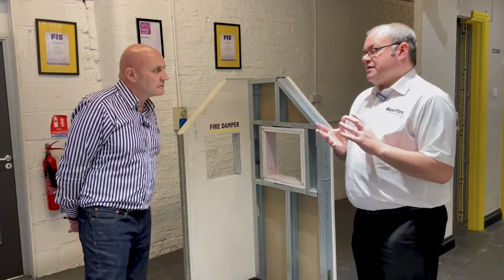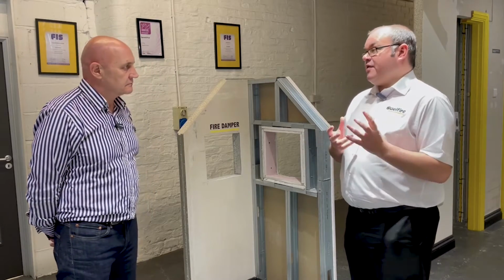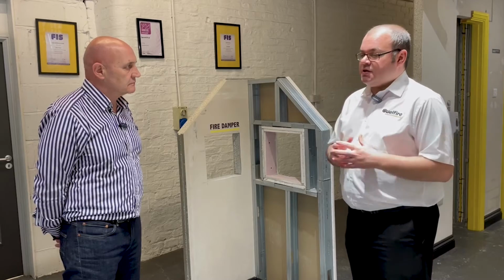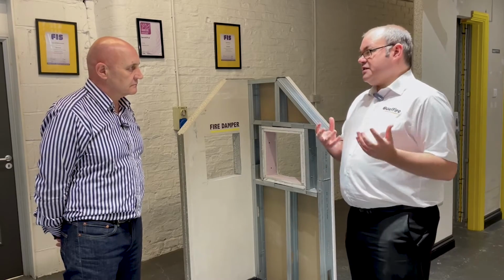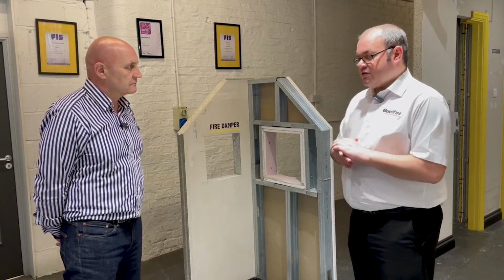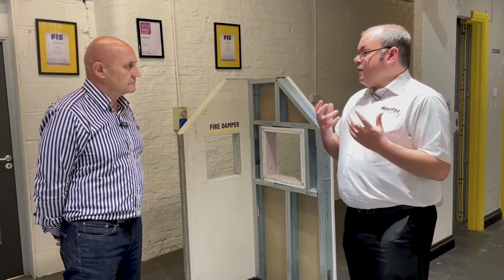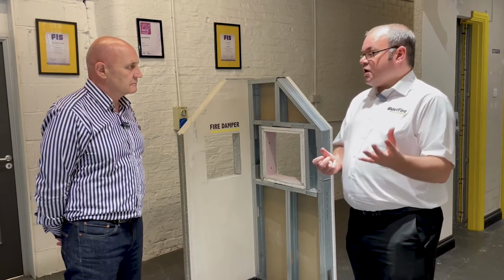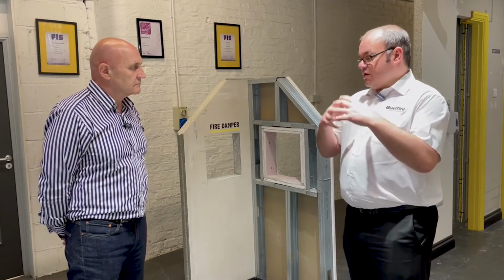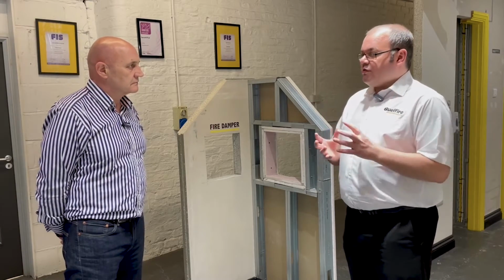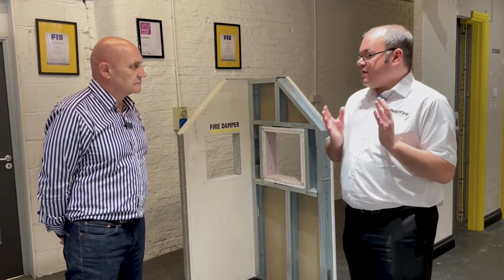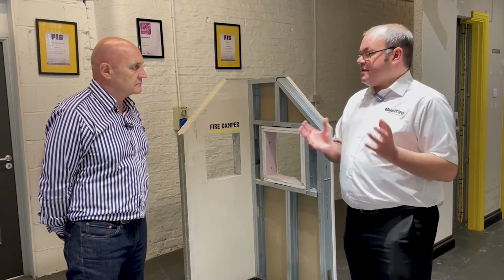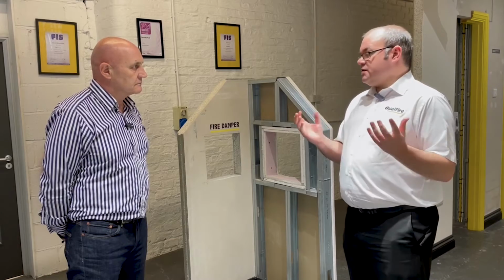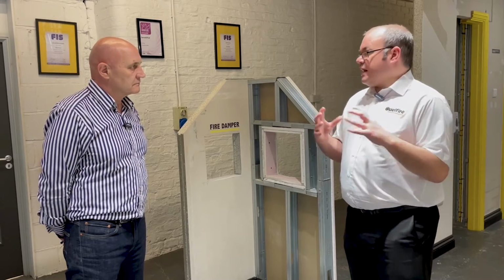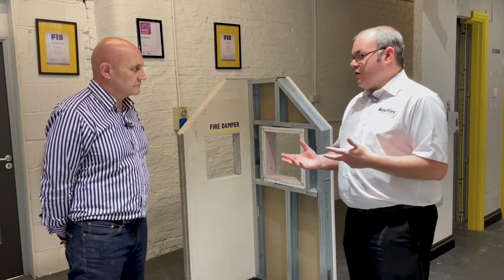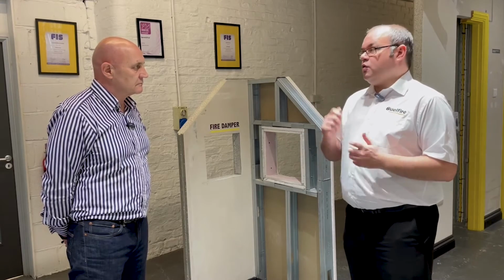Metal ducts and dampers have their own specific fire resistant test standard, and it's actually quite complex. So what we would advise for any client or manufacturer is to have a conversation with yourselves, the damper or duct manufacturer, and the client's fire consultants, just to review all the primary evidence, because dampers are a very complex subject and what can and can't be done varies depending on the project. It really takes collaboration between the damper manufacturer, yourselves, and the client to make sure you're ticking all the boxes.